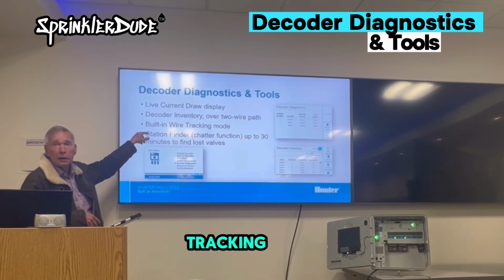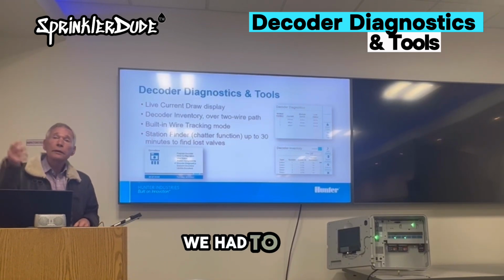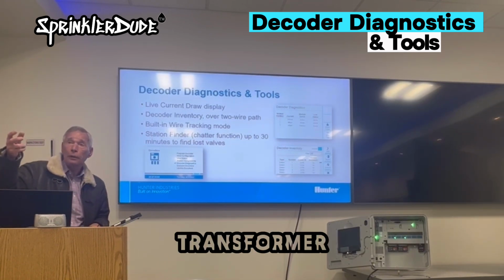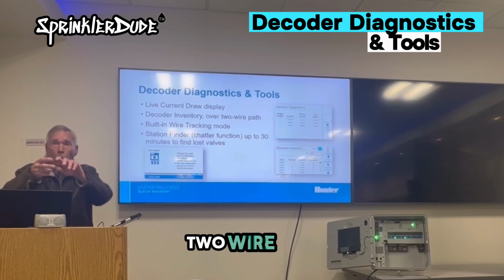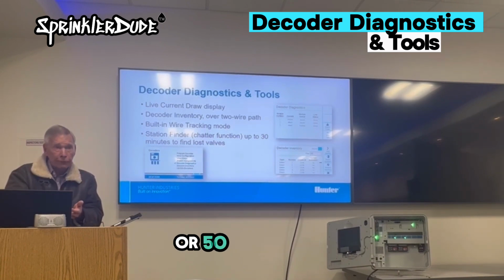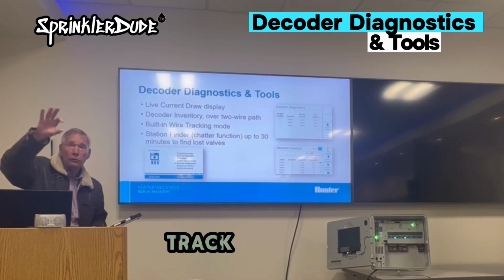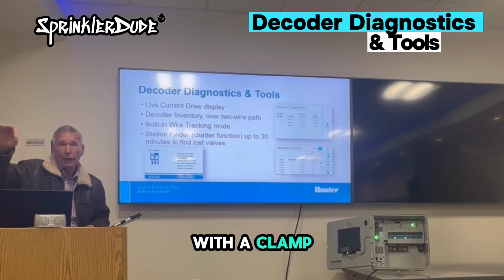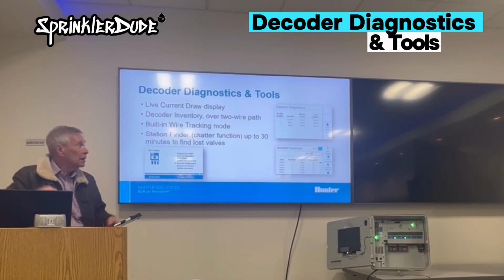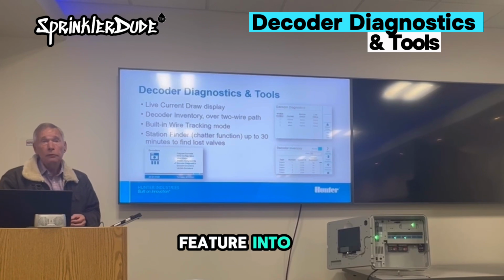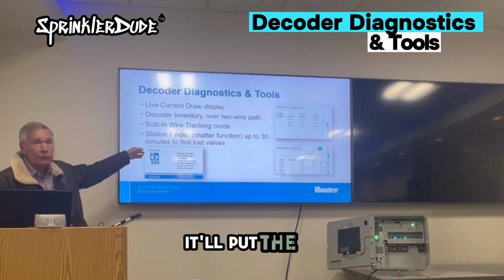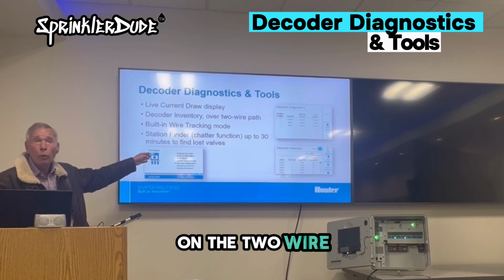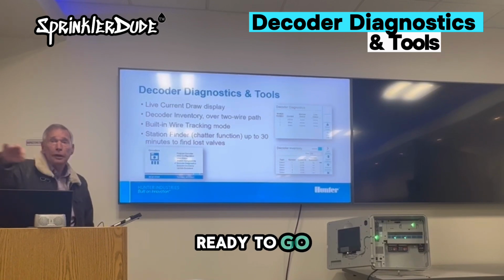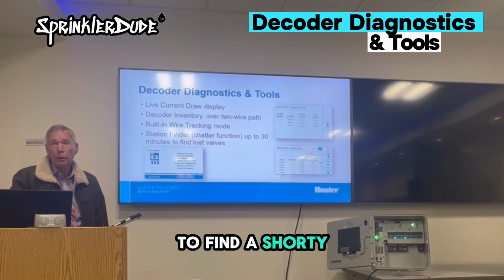Built-in wire tracking mode. So in the old days, we had to take a separate 24-volt transformer, hook it up to the 2-wire path just to put 60 or 50 hertz on it, so you could go track for shorts with an AC clamp meter. Now we built that feature into the controller. So it'll put the 50 or 60 hertz on the 2-wire path for you, and then you're ready to use a clamp meter to find a short in the earth.